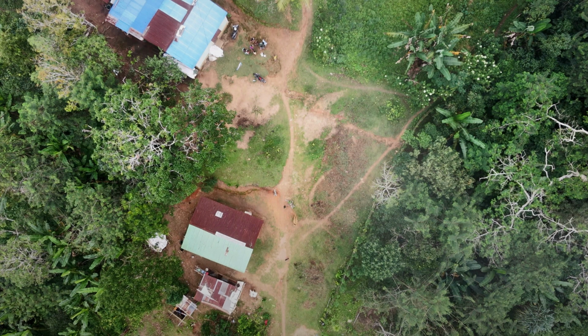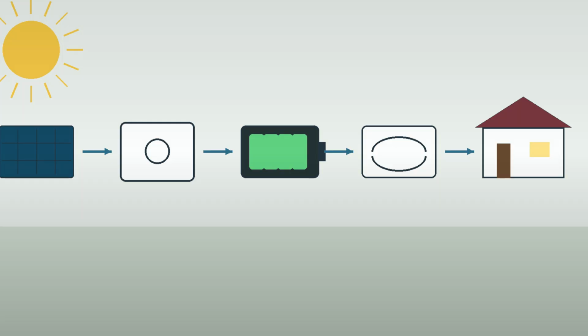Battery safety depends on chemistry. LiFePO4 is stable compared with many lithium chemistries, but it still needs a correct BMS, correct charger settings, temperature limits, physical protection, and short circuit protection. Lead-acid batteries need ventilation because charging can create hydrogen. Do not mix old and new batteries. Do not mix chemistries. Do not bypass the safety gear to make a cheap part fit.